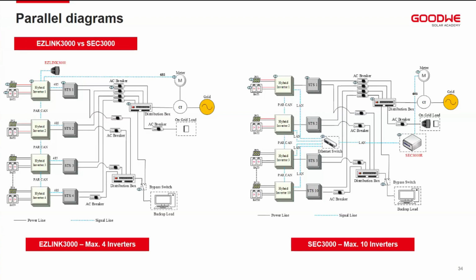If you're scaling up more than 4 pieces, then you need the SEC3000. And in this sense, you'll be doing up to 10 ET50s or 10 ET40s. So your maximum, you can do 500 kilowatt. The battery rating can go up to 3 megawatt hour. Yes, so that's on the maximum side.